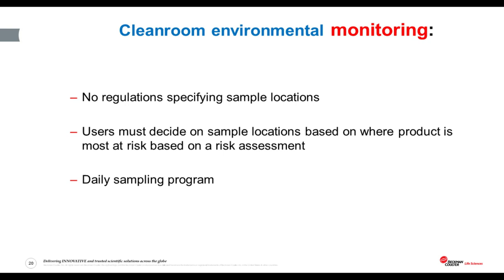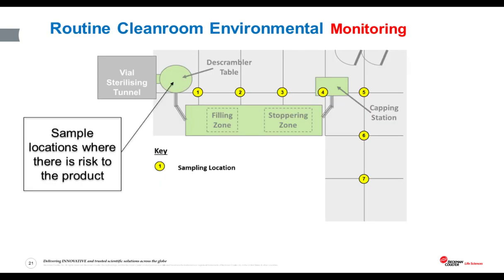Now we come to clean room environmental monitoring. For monitoring, there are no hard and fast rules — just that the user must make a risk assessment of where the product may be exposed to airborne contamination in the manufacturing process, and set sampling locations at these points for their routine environmental monitoring program. Taking another look at the same example, in this theoretical case the user looks at their manufacturing process, decides on those locations where the product may be at risk, and lays out their sampling program accordingly. You'll notice these sampling locations for routine environmental monitoring are in very different locations to those used for classification. Please avoid using the same locations you do for classification for routine monitoring — it's not how it should be done.